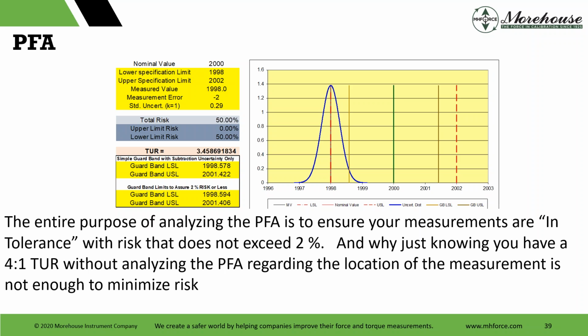And why just knowing you have a 4-to-1 TUR without analyzing the PFA regarding location is not enough to minimize the risk. Here's one where our TUR is 3.45 and our total risk is 50%. And why is that? It is because our measurement is right on the line. We could have a TUR of 20,000 to 1, and it would still be 50% if we drew that line. If we drew the curve, 50% of our data, of that normal curve, that probability distribution, would be outside of the line.